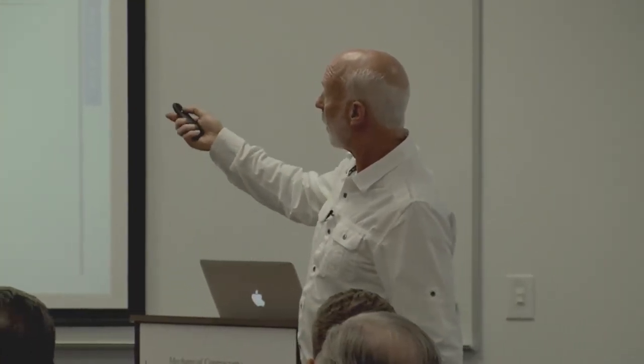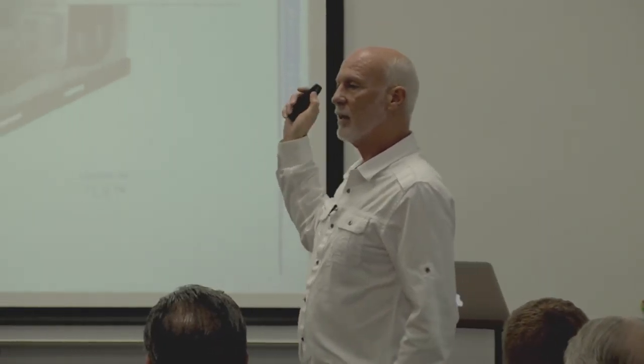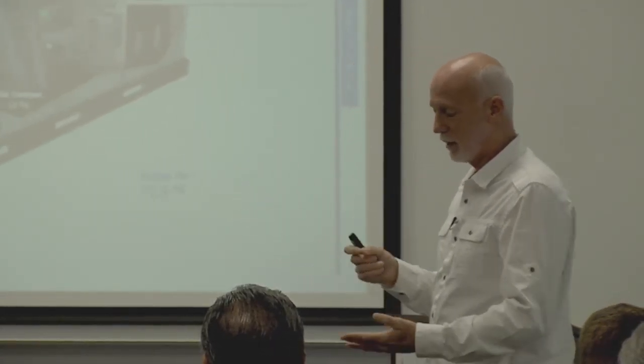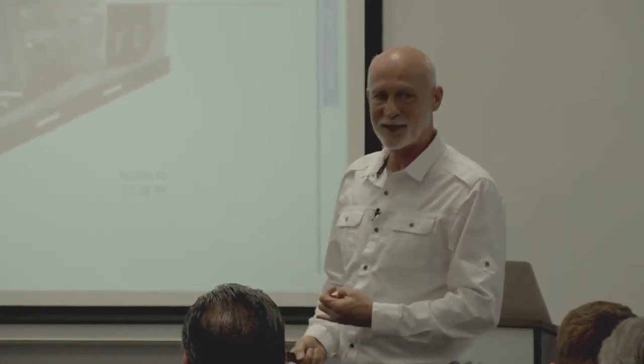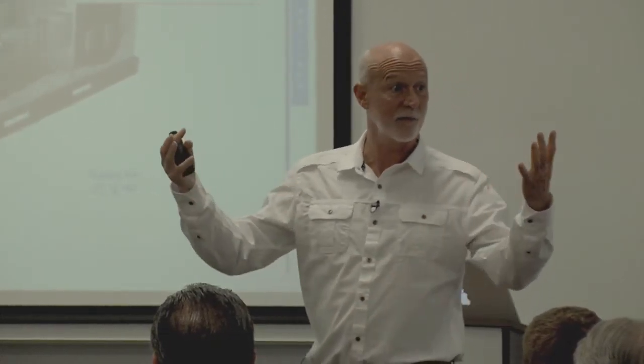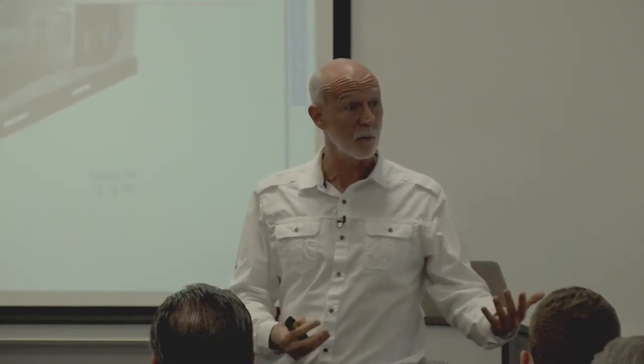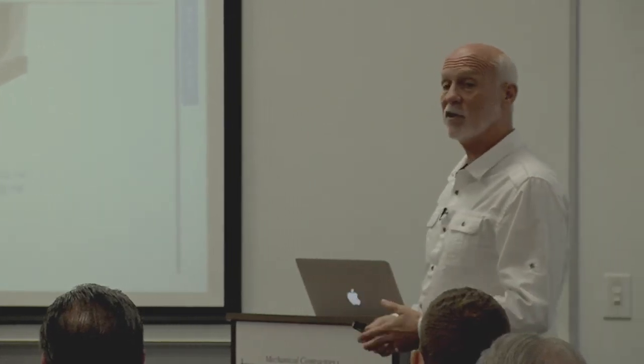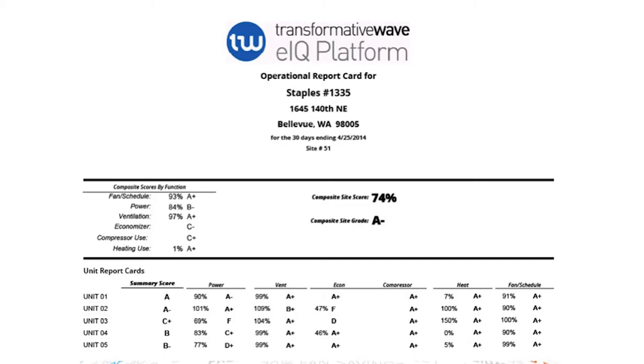So while we call it a fan belt fault, it's actually more than that. It's an example of getting energy benefits but also, in this case, a comfort benefit, since this big 20-ton system didn't go offline for weeks for repair or replacement - not to mention the costs associated with that repair.